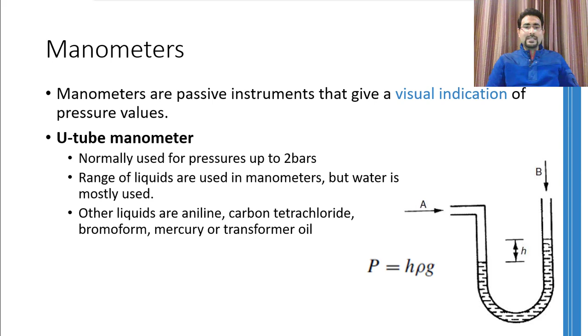As the liquid becomes denser, the sensing range will increase, but the sensitivity will decrease. Well type and incline type manometers can have much more sensitivity as compared to a simple U-tube manometer. You can see over here that if pressure is applied from this side and the liquid moves downwards a bit, then on the other side the liquid will rise considerably because the size of this side is quite thin as compared to the first side.